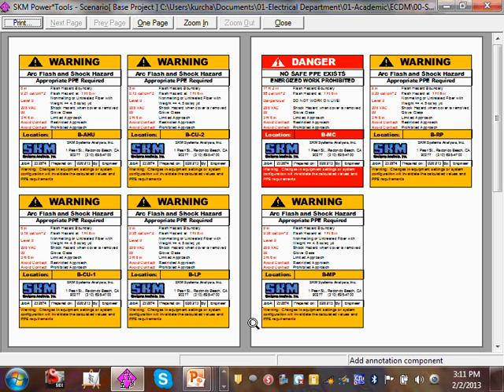So the MCC, not short circuit, it was 32. The short circuit was 32. It was not a big deal. There is no circuit breaker ahead of it. I did not put a circuit breaker ahead of it because the utility owned the transformers, and typically they put their circuit breakers on the primary side. So I assume there is no circuit breaker here. Then this means if you are to work in the MCC, you better de-energize the equipment because there is no circuit breaker that can protect you from arc flash.